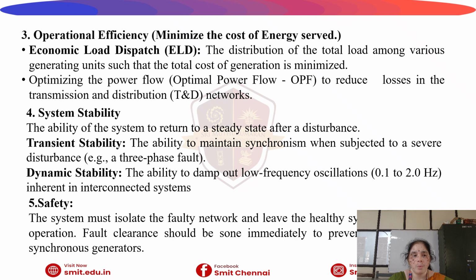The next important requirement is operational efficiency, that is, minimizing the cost of energy served. Economic load dispatch is to be followed. It is the distribution of the total load among the various generation units such that the total cost of generation is minimized. Optimizing the power flow reduces the losses in the transmission and distribution network.